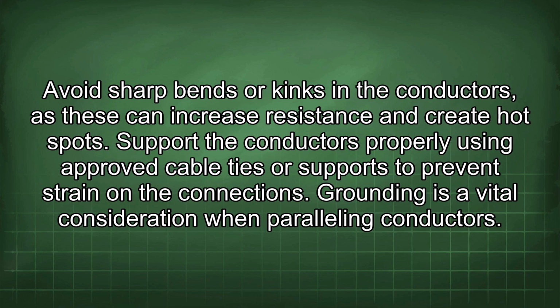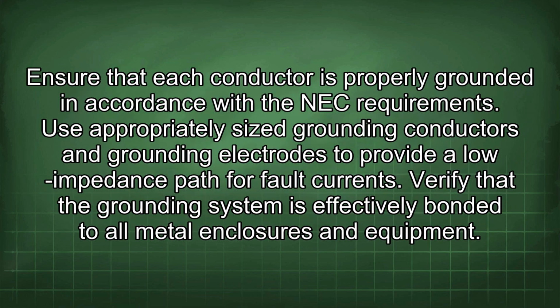Grounding is a vital consideration when paralleling conductors. Ensure that each conductor is properly grounded in accordance with the NEC requirements. Use appropriately sized grounding conductors and grounding electrodes to provide a low impedance path for fault currents. Verify that the grounding system is effectively bonded to all metal enclosures and equipment.